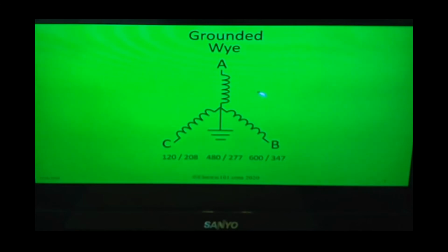Now, in this circuit right here, you're going to measure between A phase and B phase, A and C, and you get 208 volts. You measure A to B, you get 208. Okay, you measure C to B, and you get 208. But now, if I measure anything like, say, A to neutral, I measure C to neutral, I measure B to neutral, it's going to be 120 volts for each one. So this is the most common transformer you're going to see.